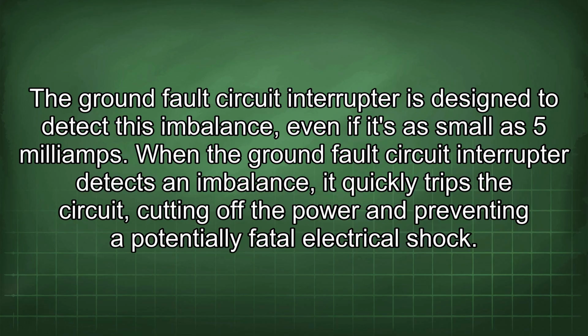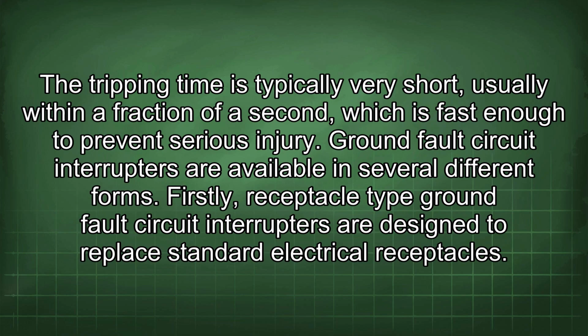This creates an imbalance in the current flowing through the hot and neutral conductors. The ground fault circuit interrupter is designed to detect this imbalance, even if it's as small as 5 milliamps. When it detects an imbalance, it quickly trips the circuit, cutting off the power and preventing a potentially fatal electrical shock. The tripping time is typically very short, usually within a fraction of a second, which is fast enough to prevent serious injury. Ground fault circuit interrupters are available in several different forms.